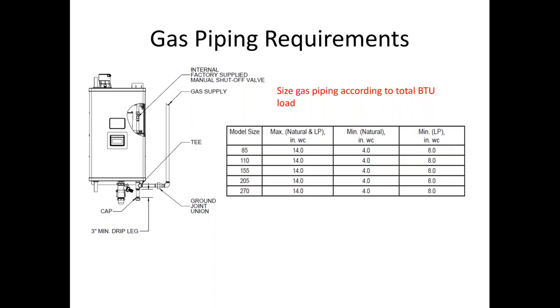The next portion we're going to go over is the gas piping requirements. You're going to need to size the gas piping in accordance with the BTU load, but there are some min maxes for the inches of water column for these products to run correctly. Real life story: I've run into issues with these, only seeing the static pressure. I put my manometer on there and saw it hold at 5.5 inches of water column and thought, okay, why isn't this boiler firing? We also want to double check the dynamic pressure. Turn other fixtures on. In the case I was speaking of, whenever the boiler would go to light, the gas line was dropping into a negative, down to like negative 2.4 inches of water column. There was a faulty regulator and a bad meter in the system leading to that.